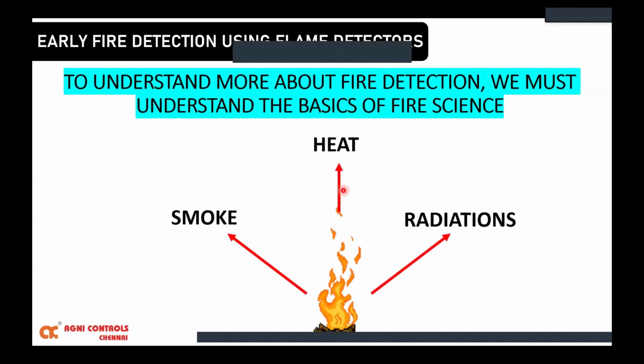So to understand fire detection, we must understand the basics of fire science. Fire emits energy. Energy is in the form of heat, smoke, and radiations. The amount of smoke, heat, or radiation depends on what fuel source it's burning. If it's a class A fire, which is wood and ordinary combustibles, it's going to be smoke and heat. And for a class B fire, which is flammable liquids and gases, it's going to be radiations, which will come out first.